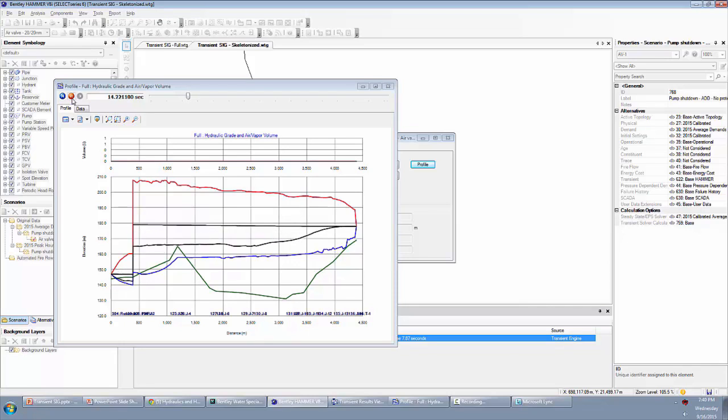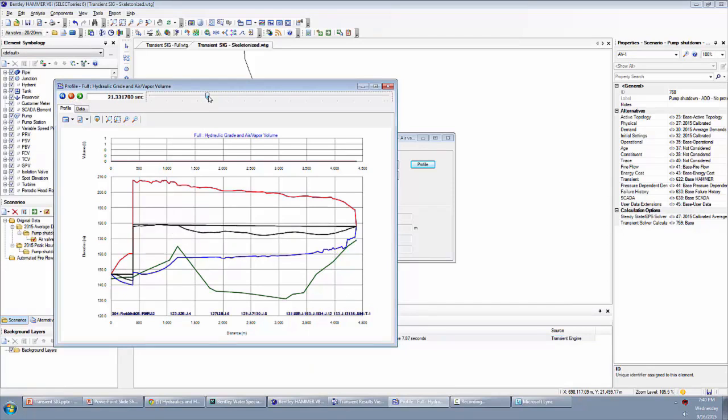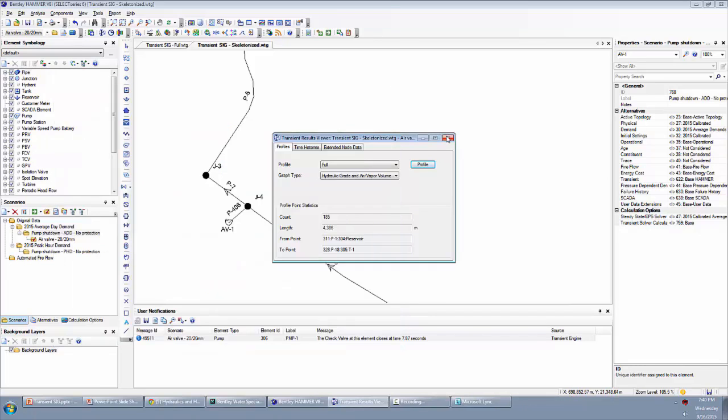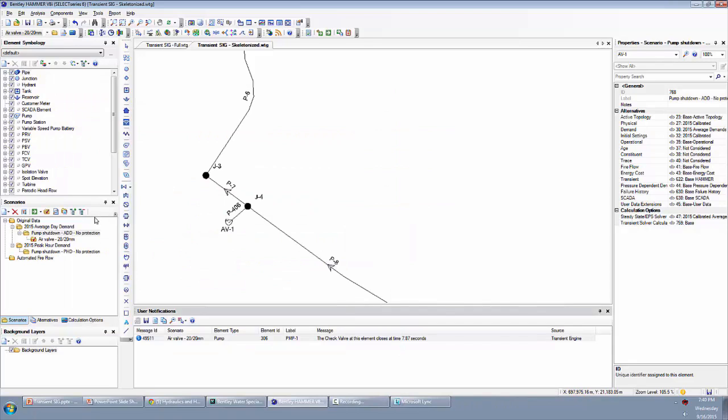If we continue graphing there, we can see it looks pretty good, not too bad. But if we wait a little bit, just fast forward a little bit here. Okay, so right here, similar to our vapor pocket collapse, we have an air pocket collapse occurring from the air that was let in through the air valve. And that has a similar effect. It bounces back and forth. So we didn't do all that much better with the 20 millimeters. So let's try 40 millimeters.